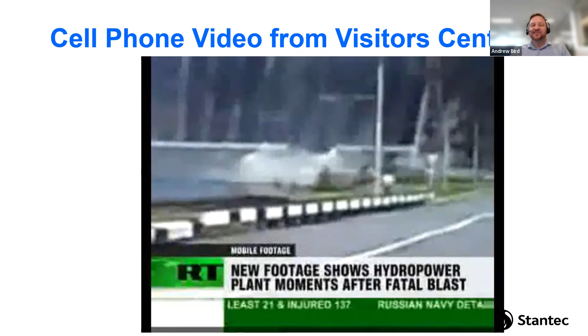So Barry Hill's saying, what happened to the copper? I think you said in your presentation it was all gone. Do we have any ideas? Because of the overspeed event and the short circuit torque, it came off the end of the rotor. It just flew off, and then it ripped the stator right off. The rotating parts of the rotor just ripped the stator and the foundation. The bearings twisted off, and the stator just went.